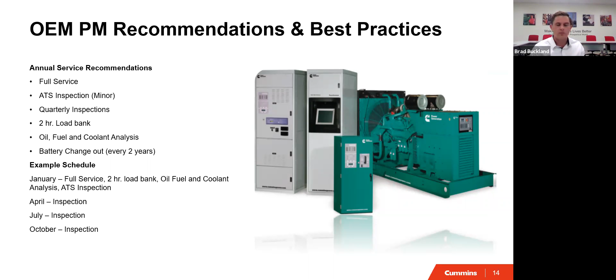So a basic schedule would break out like this: the January service would be your annual PM2 with the 2-hour load bank, the oil, fuel, and coolant analysis that detects anything wrong, and the ATS inspection. Then April, July, and October would be the actual generator inspections. So you're looking at 4 times a year someone coming out—January being a bit more intrusive with the load bank performance testing, the 2-hour load bank. This is really how we get around using the building load test, saving your tenants' time and not inconveniencing anyone at all.